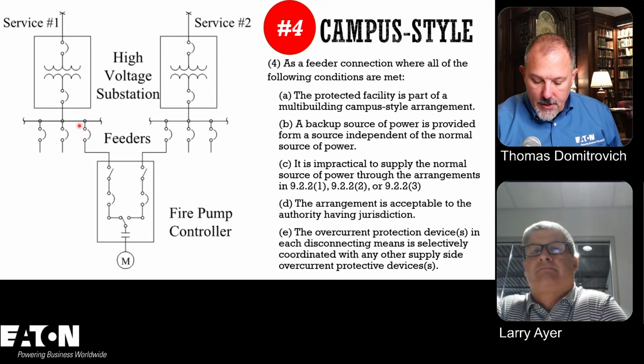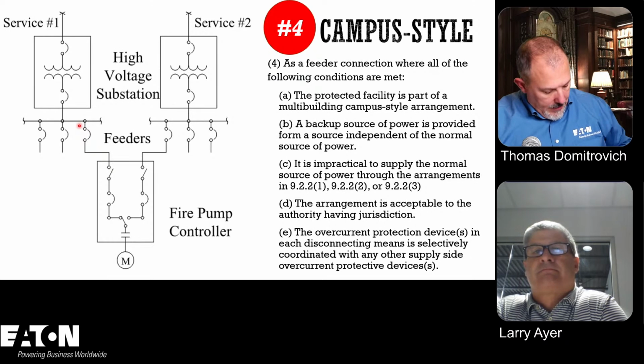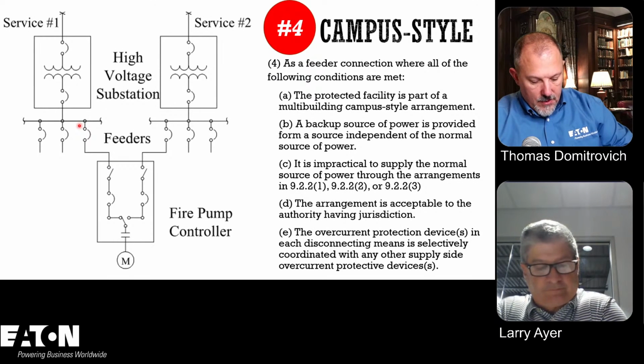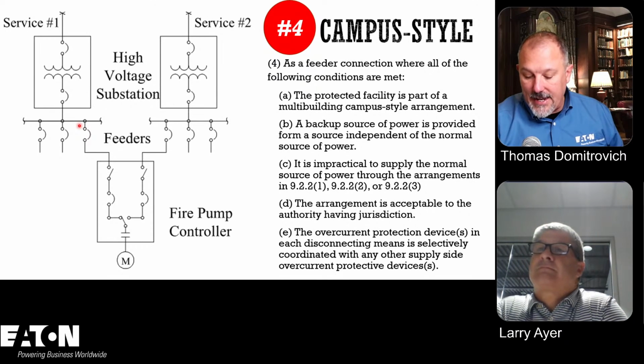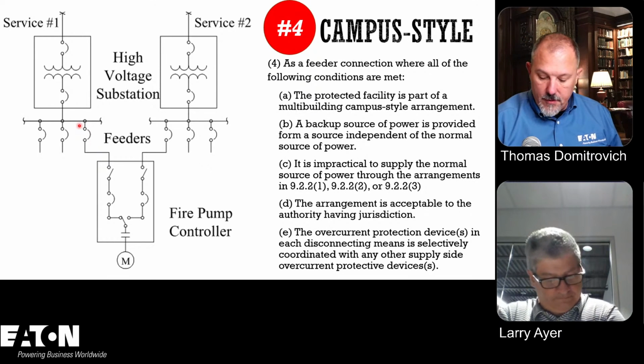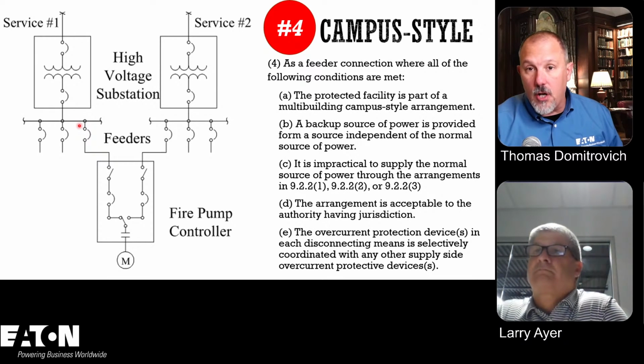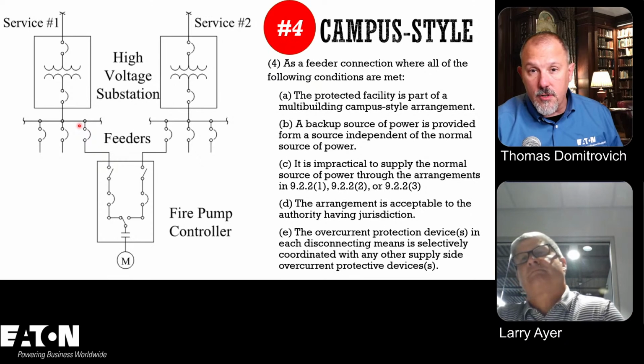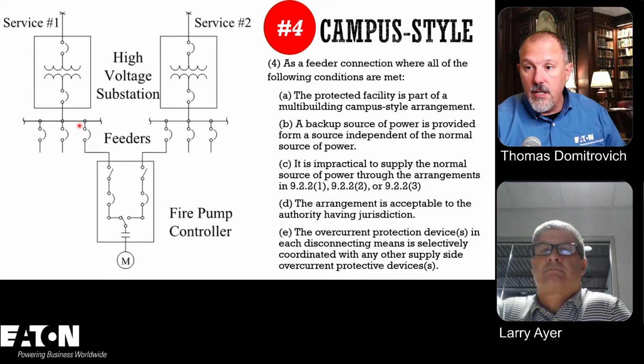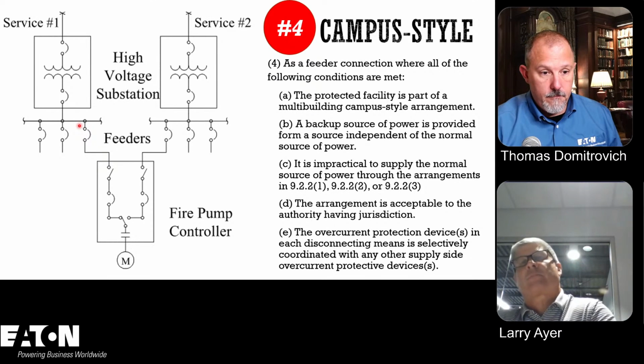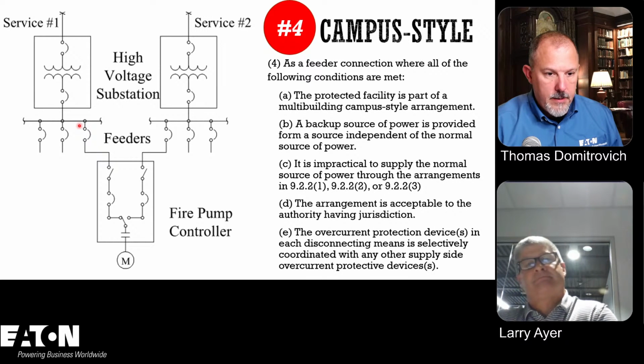Now, in what section is this? 695.3 D says on-site standby generator as an alternate source. There are three requirements. You can use a standby generator as an alternate source, but you have to address the capacity, the connection, and adjacent disconnects. So there are special requirements. You can use it as an alternate, but I agree with you, you're going to be using an integrated unit that's listed if it's your primary source. Correct. Yeah. All right.